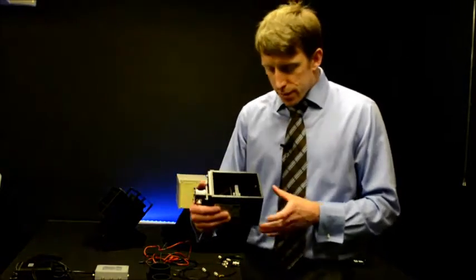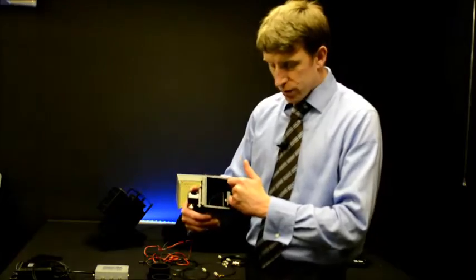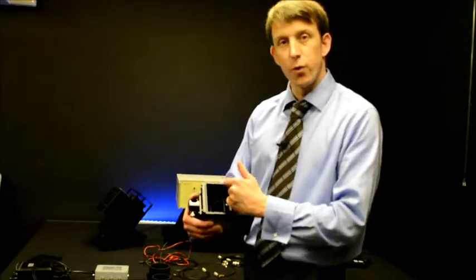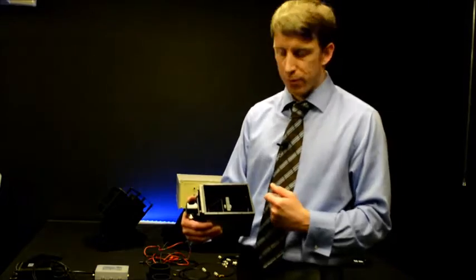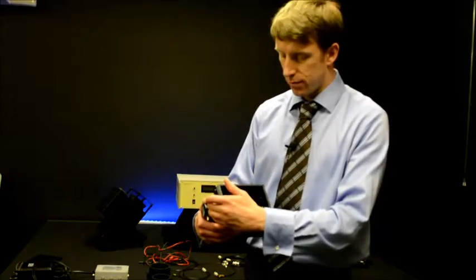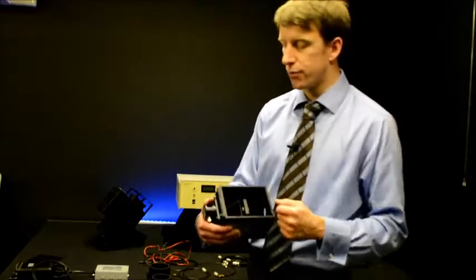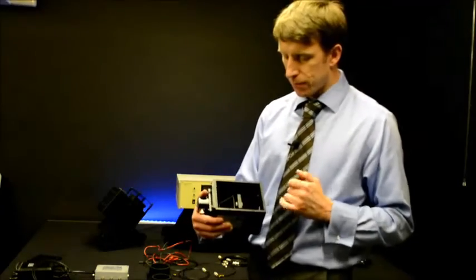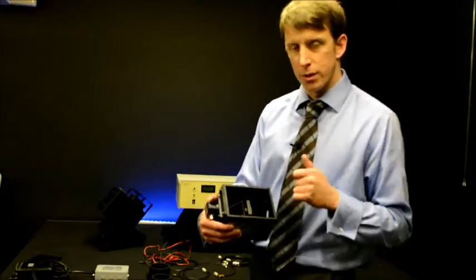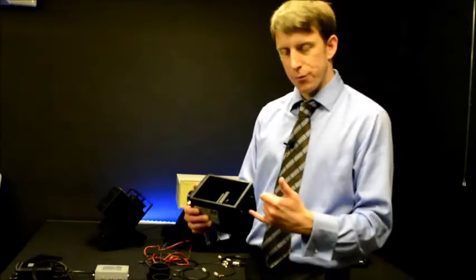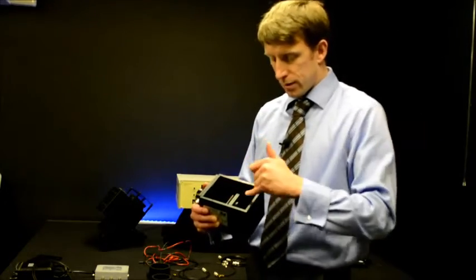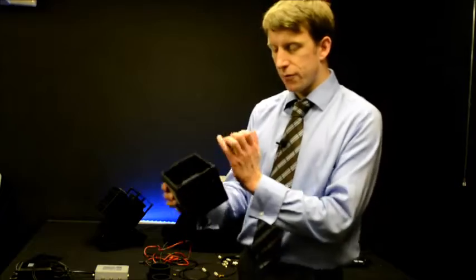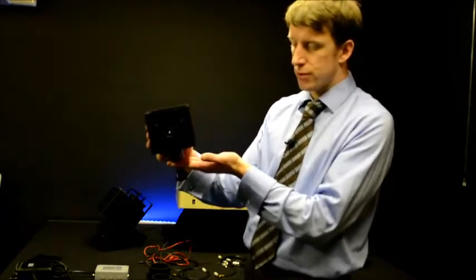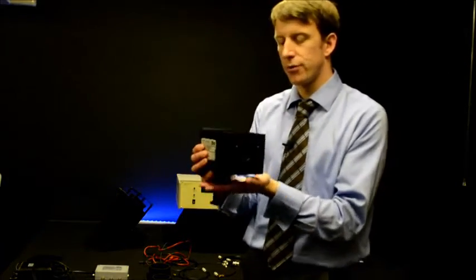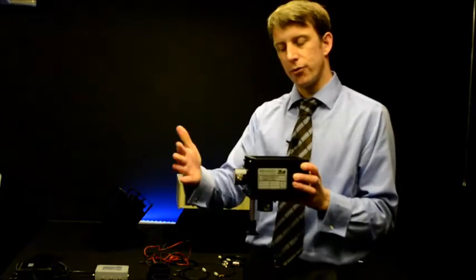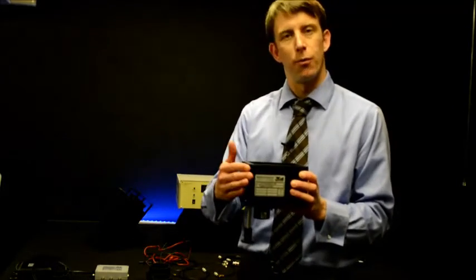The RSR unit is composed of a quartz lens which provides a 1-to-1 image of the exit slit aperture onto the detector under test, the reference diode or the radiometer under test. And there's a beam splitter, a quartz beam splitter. So light issued from the monochromator is incident upon the beam splitter. 15% of the light, or thereabouts, goes to a monitor diode at the bottom of the unit, and the remainder goes to the reference diode or the radiometer under test.